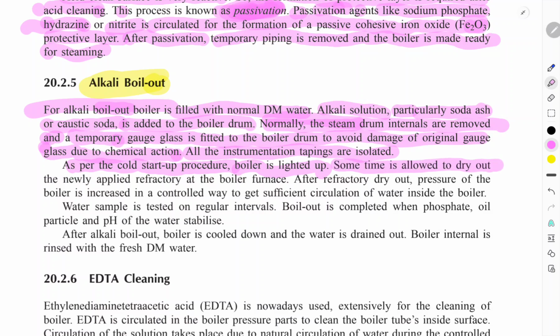Some time is allowed to dry out the newly applied refractory of the boiler furnace. After the refractory dry out, the boiler pressure is increased in a controlled way to get sufficient circulation inside the boiler. Water samples are tested regularly at intervals. The boil out is complete after the phosphate, oil and particles are gone and the pH of the water stabilizes.